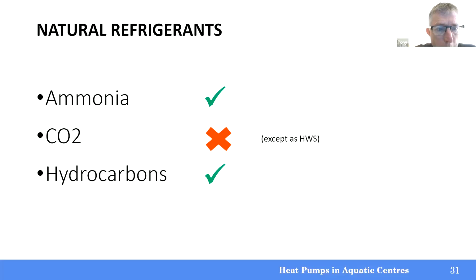They're great for that, but not ideal for heating hot water for heat pump systems in aquatic centres. So that leaves us with ammonia and hydrocarbon. Ammonia has been around for a long time and is used in many applications for heating and cooling. It has its problems with toxicity and flammability, but there are regulations around how to safely use it, and the same can be said for hydrocarbons — they are flammable, but if used correctly, can be used safely.